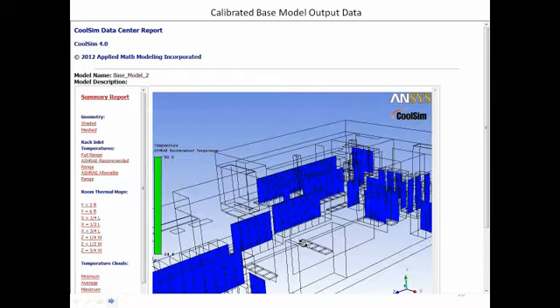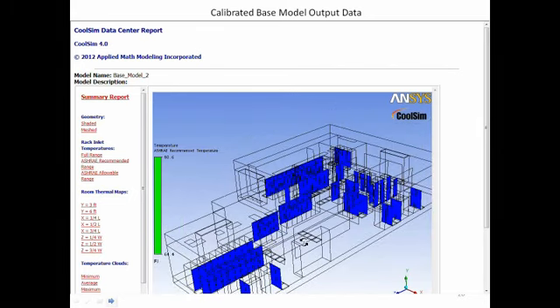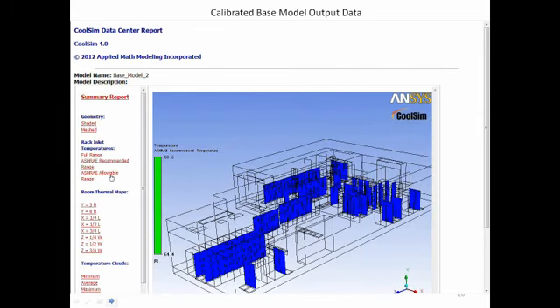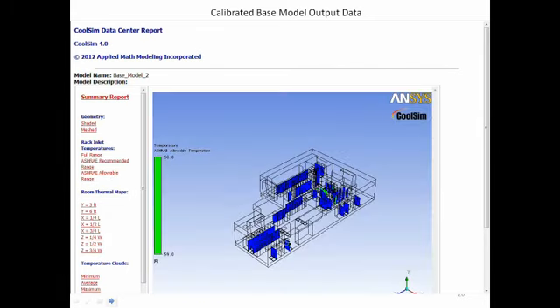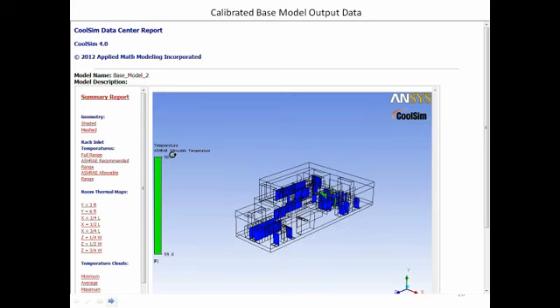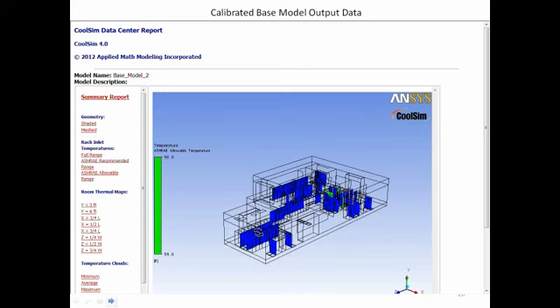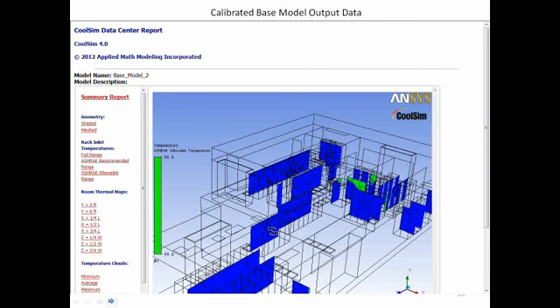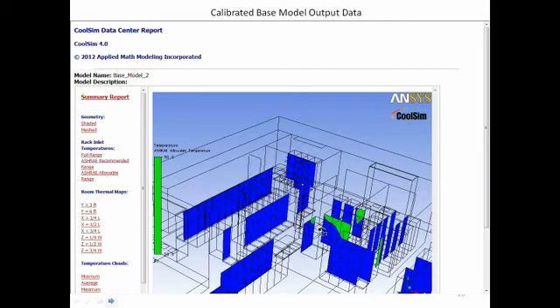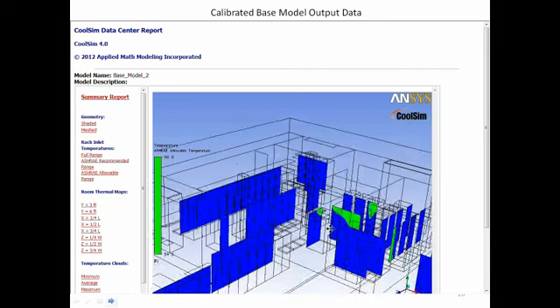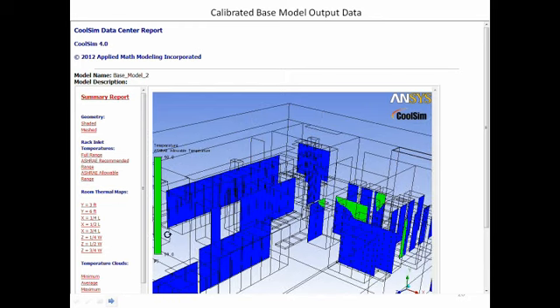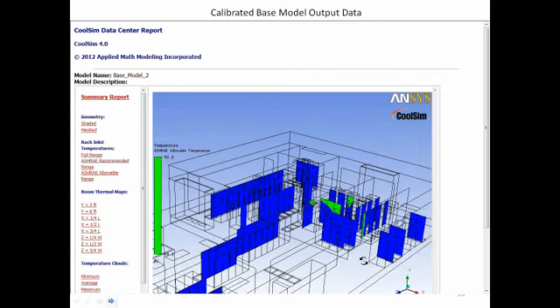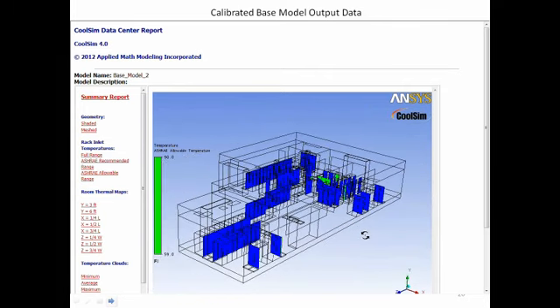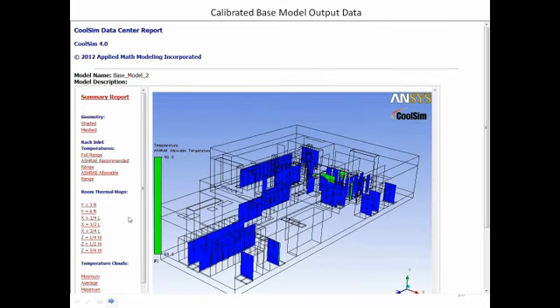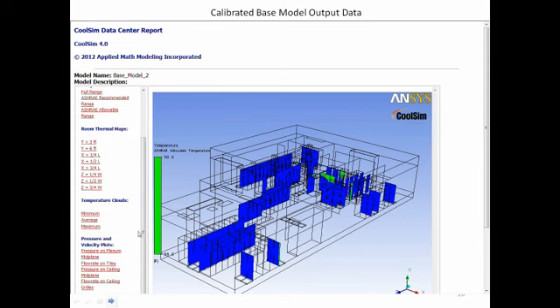So the combination of the summary report and this representation here I think are very nice. We also have one which is allowable. The allowable gives that range a little higher, 59 to 90 degrees. And you see here that some racks are beginning to come into range on the allowable. We can change these, make these anything at any time, but I think it's a nice way to look at a plot and see whether or not it's within range. We have a bunch more that we can look at.